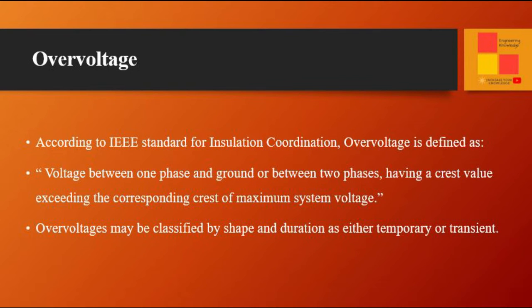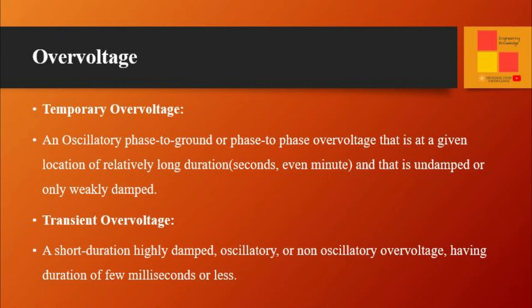Overvoltages may be classified by shape and duration as either temporary or transient. Temporary overvoltage can be defined as an oscillatory phase-to-ground or phase-to-phase overvoltage that is, at a given location, of relatively long duration — in seconds or even in minutes — and that is undamped or only weakly damped.